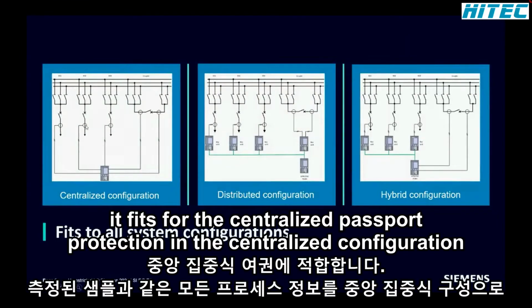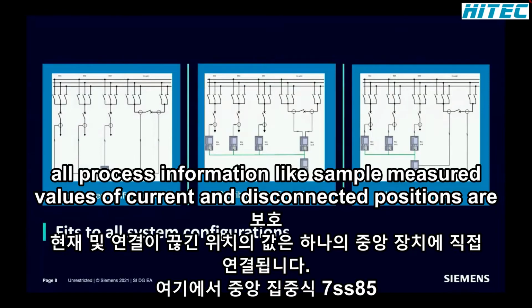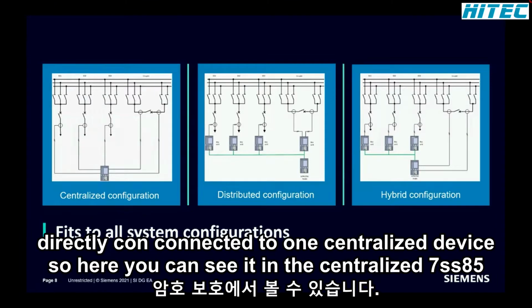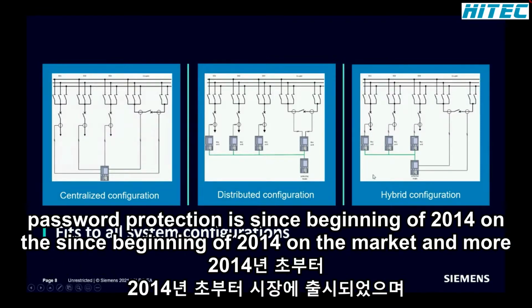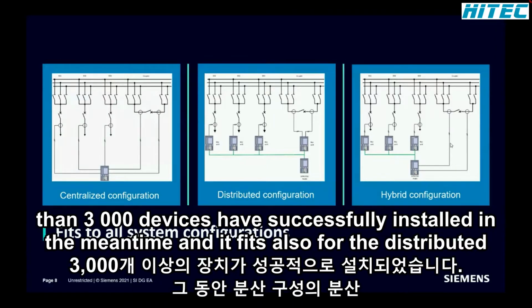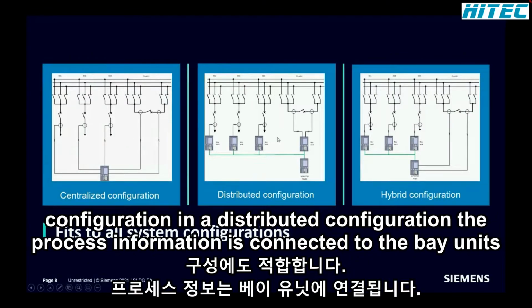It fits for the centralized busbar protection. In the centralized configuration, all process information like sampled measured values of current and disconnector positions are directly connected to one centralized device. So here you can see it. The centralized 7SS85 busbar protection has been on the market since the beginning of 2014, and more than 3,000 devices have been successfully installed in the meantime.